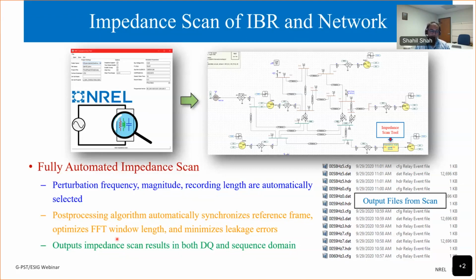So even if the data you have scanned or recorded is for 1 second during that perturbation, the tool will perform FFT analysis only on a time window selected to minimize the leakage errors, because there are multiple frequencies involved here. There's a fundamental frequency, 60 hertz or 50 hertz. There's a perturbation frequency that you're injecting. There's a coupling frequency. So the tool will optimize the FFT window to minimize the leakage so that we get a more accurate scan. And finally, it outputs the impedance in both DQ and sequence domain: the DQ impedance, or positive sequence and negative sequence impedance, as well as the coupling between the two.